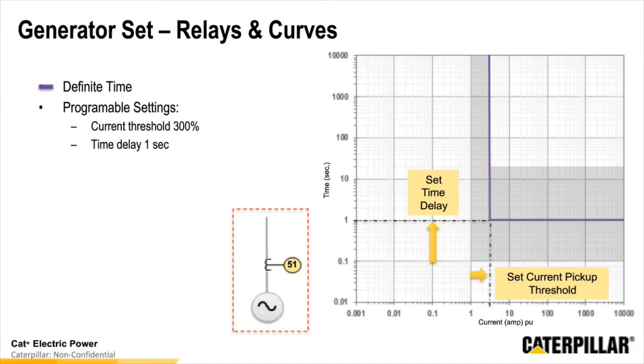So a more common setting that you may see is setting the unit to 300% for 1 second. Now, our Caterpillar generators, typically at 60 hertz, are rated for 300% for 1 second. For a 50 hertz product, that may, or sorry, 300% for 10 seconds. A 50 hertz product would typically be around 250% for 10 seconds. But you can work with the dealer, your CAT dealer, to understand what your specific unit's capabilities are. So in this application, we've set the units to 300% again for 1 second.